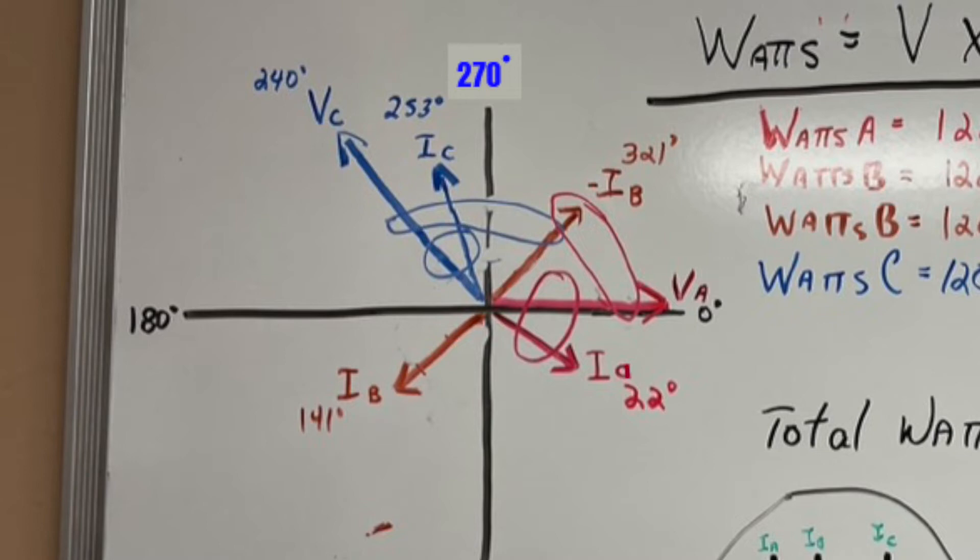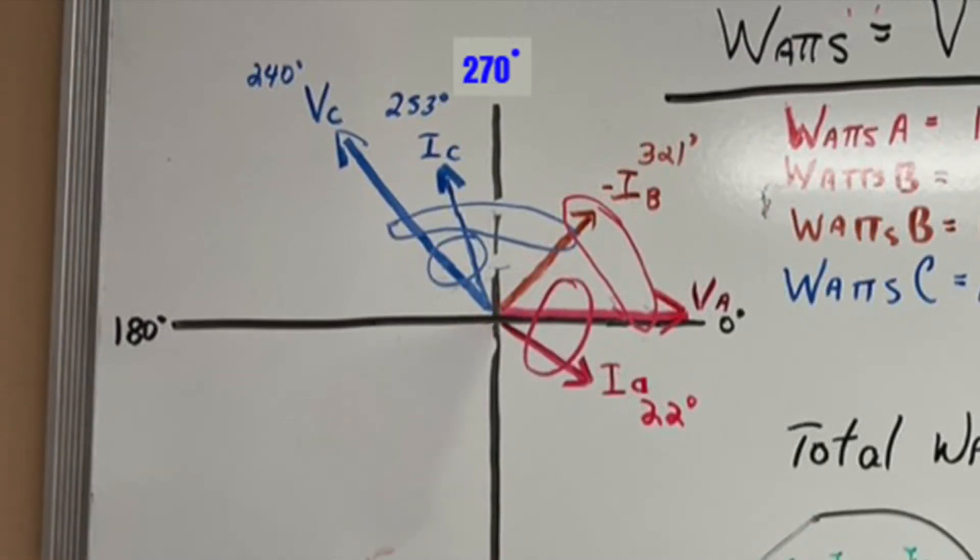So in the meter, if you remember, we have to reverse this current. It's reversed in the meter internally. So we're going to take this 141 degrees and flip it 180 degrees and it'll now become negative IB at 321 degrees.